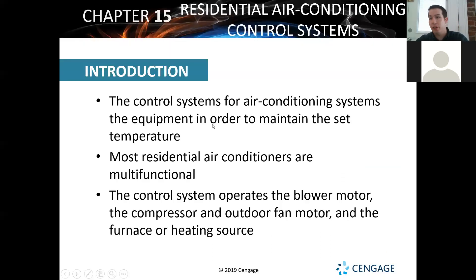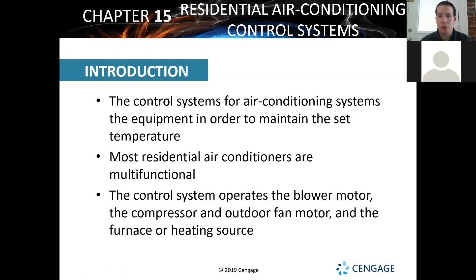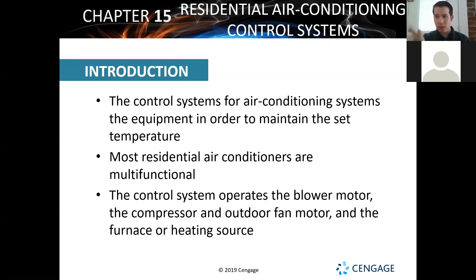Going into residential air conditioning controls. When you start out in HVAC, the control you'll come most in contact with is your thermostat. The other things are IFC boards or control boards — anything that has to do with solid state. We have to learn how to measure, work with, and test them. Some boards have self-diagnosing lights; some let you hook up a computer or flash drive to run a diagnostic. Residentially, the most common approach is checking voltages — high and low — and testing all your different components.